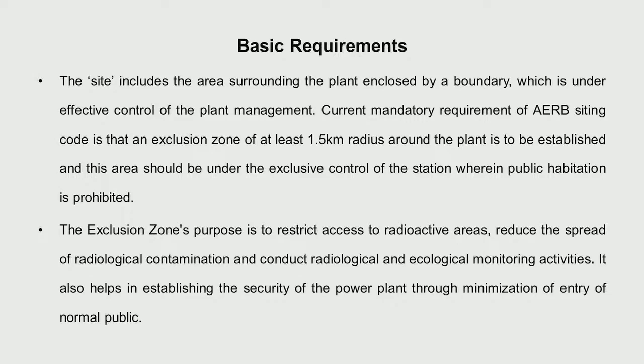Now, what is the site? It includes the area surrounding the plant which is under the management's control. We have specified a circle of about 1.5 kilometer radius around the plant which is totally under the control of the plant authorities. In this exclusive area no other establishment can be there — no houses, nothing. Only the plant and its associated establishments will be there. This is called the exclusion zone — the public is excluded.